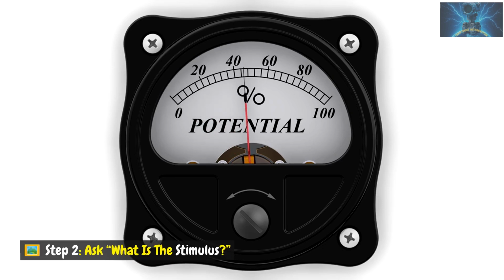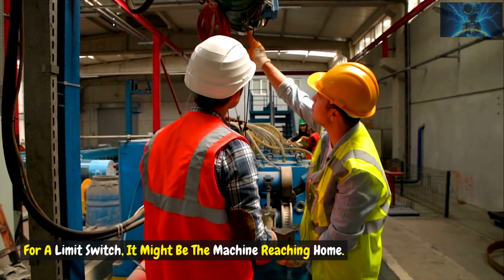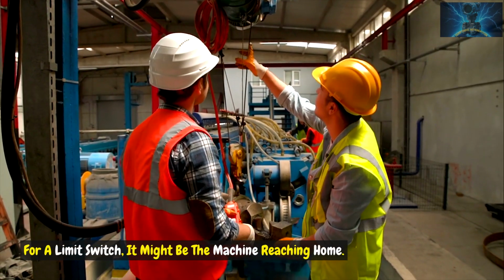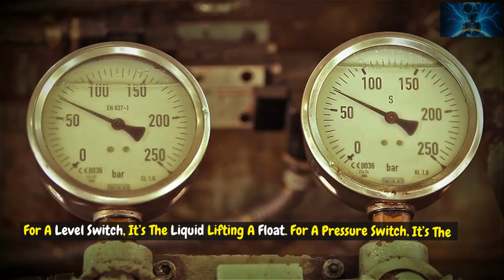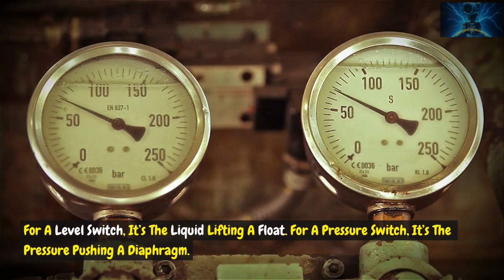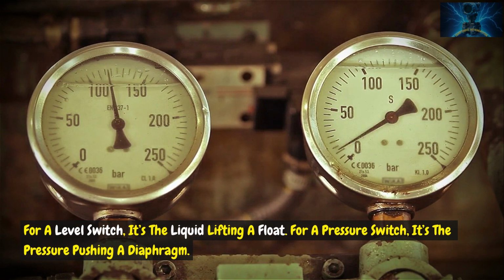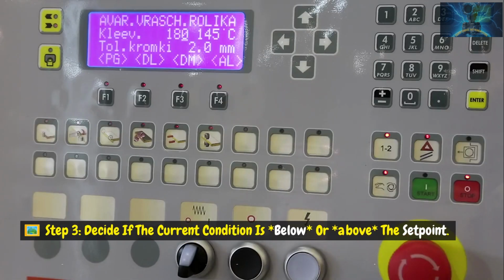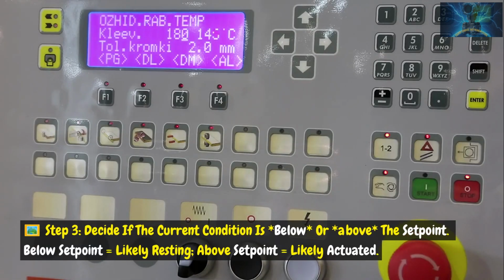Step 2. Ask, what is the stimulus? For a limit switch, it might be the machine reaching home. For a level switch, it's the liquid lifting a float. For a pressure switch, it's the pressure pushing a diaphragm. Step 3. Decide if the current condition is below or above the set point. Below set point equals likely resting, above set point equals likely actuated.